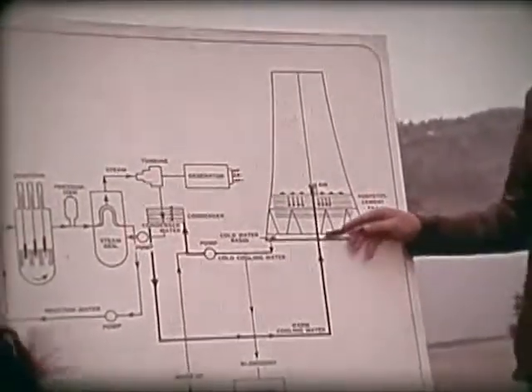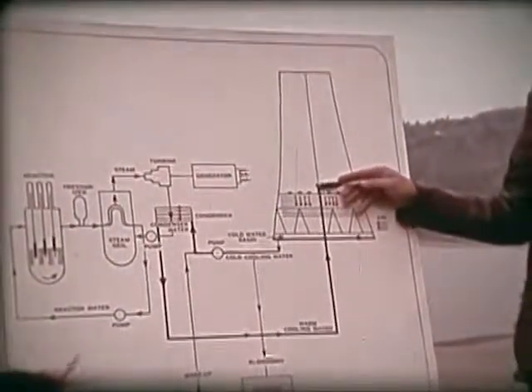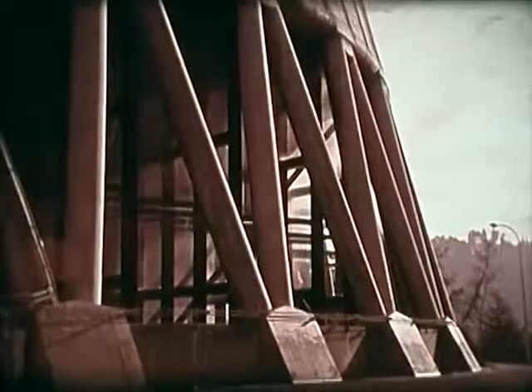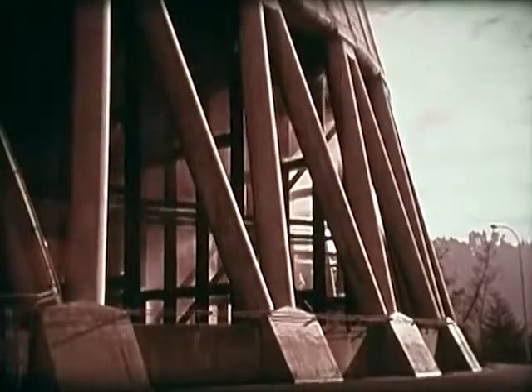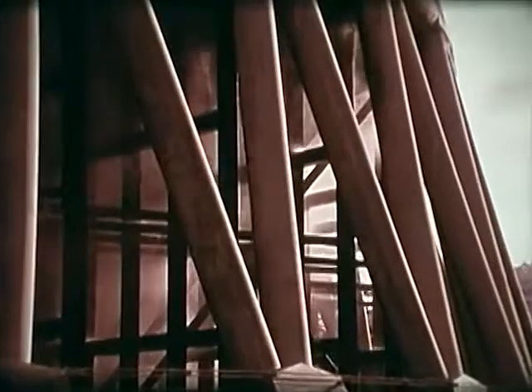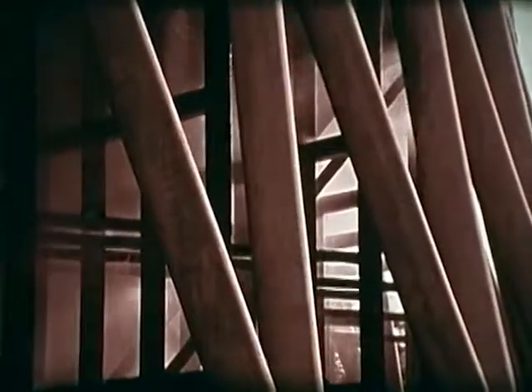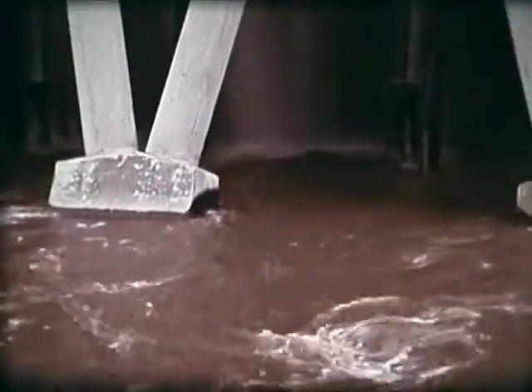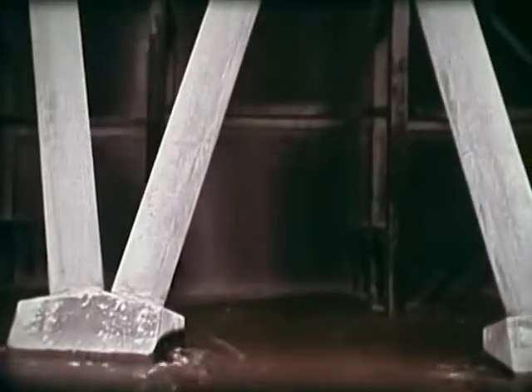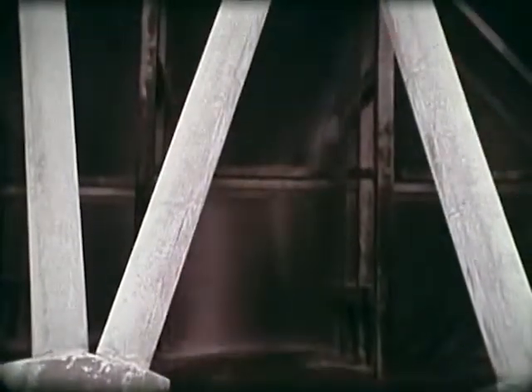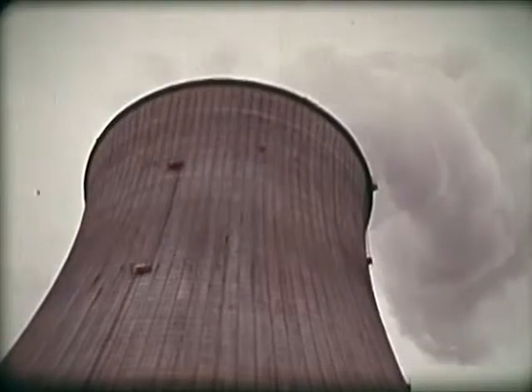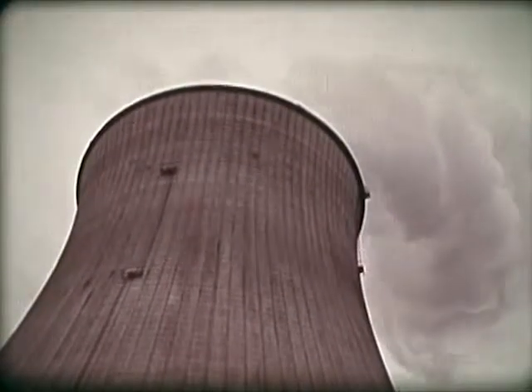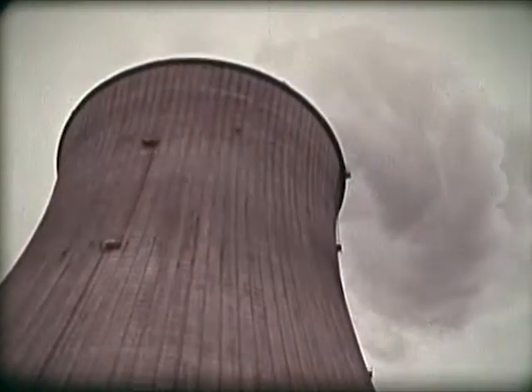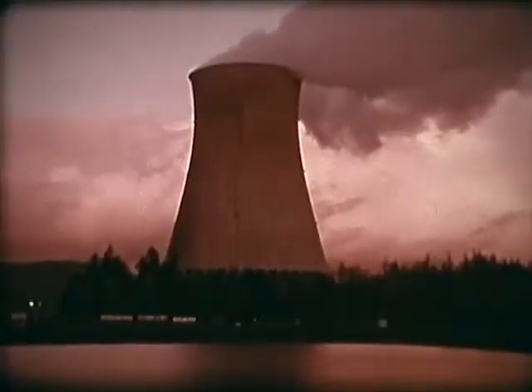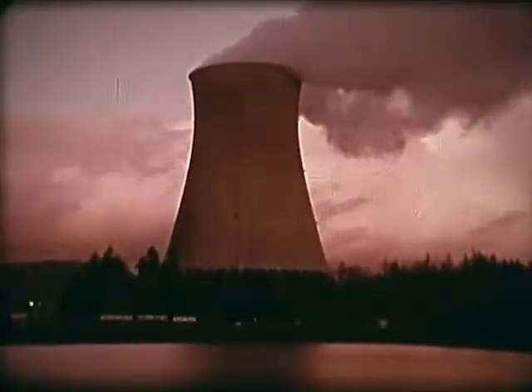If you'll notice, the water only goes up about a fourth of the way up the tower, and then it is pumped through large headers where it is sprayed and broken up into fine droplets and falls back down to the basin. The tower is open at the bottom, where air enters, flows up through it just like a large chimney by natural draft, and the water gives up heat to the air, producing the large plume of water vapor coming out the top.